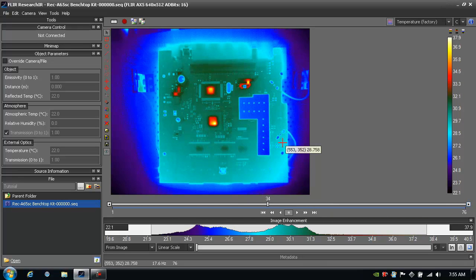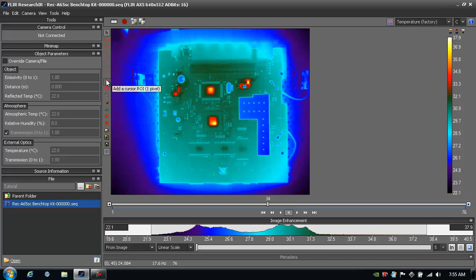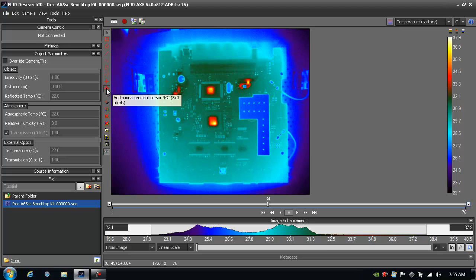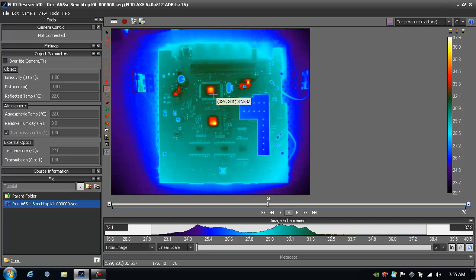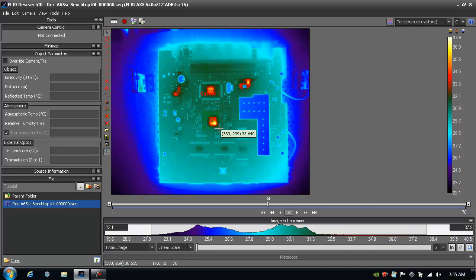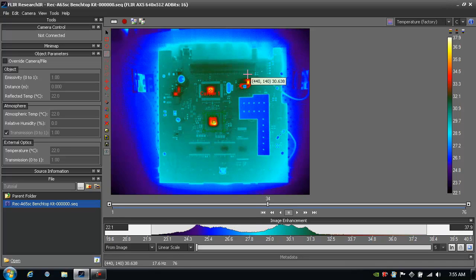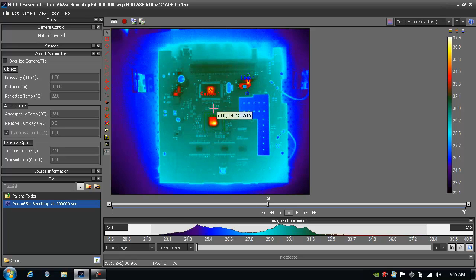Let's add some analysis tools. Now we saw earlier that anywhere we move our mouse we get a temperature value per pixel. We can also add a box, circle, line, single pixel spot, or a 3x3 pixel spot. I like this 3x3 pixel, it's kind of easy to grab, so I'm going to put that kind of maybe right there in the middle of this hot chip. And I'm going to grab a box, and maybe I'll add that around here so I can see that box. And then I'll grab a line profile as well, and maybe I'll throw that on this, maybe a diode or a resistor up here and kind of put that across there.